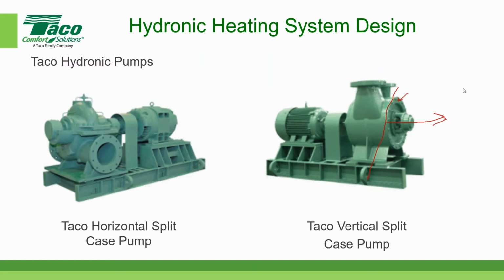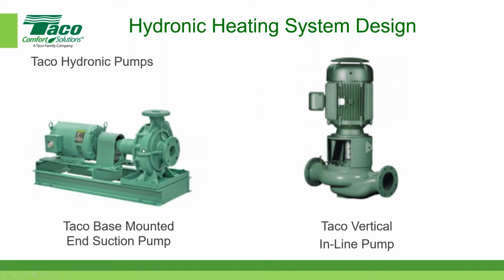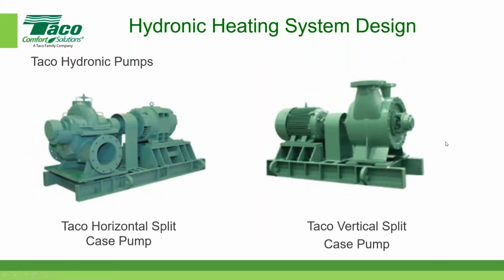So whether it's a horizontal split case, a vertical split case, let's go back to the previous one, an end suction pump or vertical inline, all of the Taco pumps allow you to keep the pump connected to the piping system if you have to service the pump. You do not have to disconnect the pump from the piping system in order to dismantle the pump and take the internal components out. And that's a major benefit if you're servicing any one of these pumps.